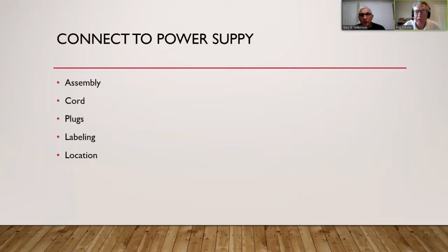So your green wire would go on the G. Your white wire would go on the W, and you see how convenient that is because they got G and W. Right. And then your ungrounded conductor or your hot wire or the dark colored conductor, black normally or red, would be on the one that's not marked.